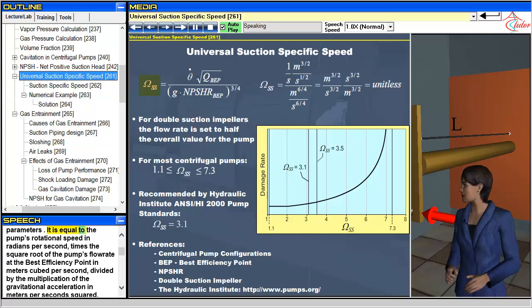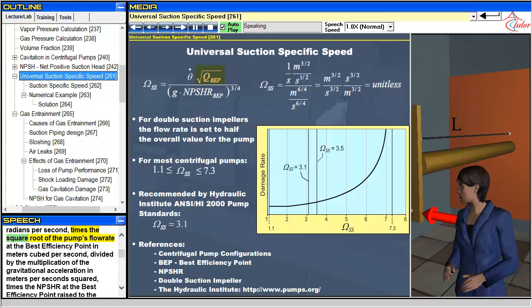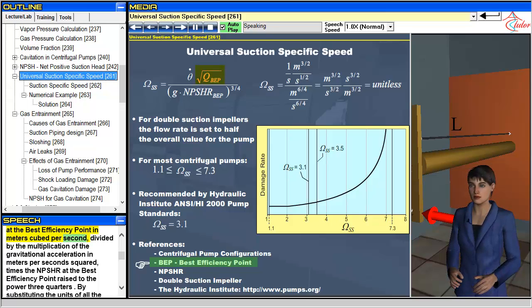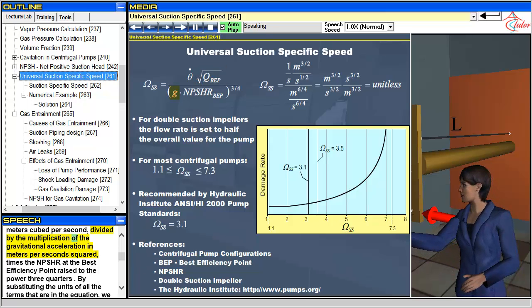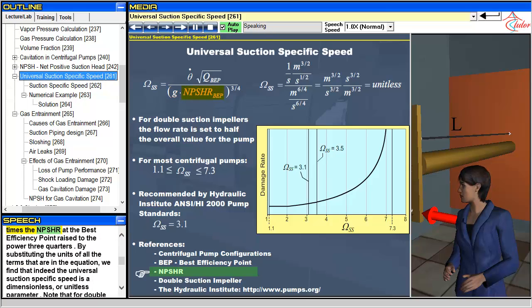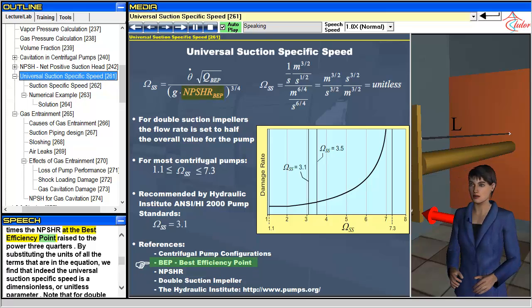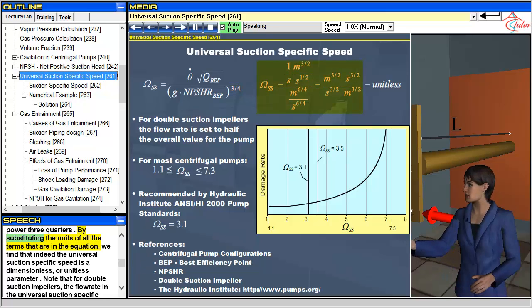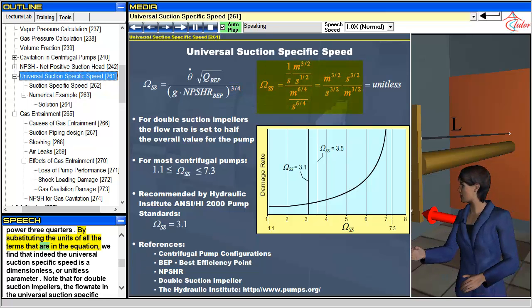It is equal to the pump's rotational speed in radians per second times the square root of the pump's flow rate at the best efficiency point in meters cubed per second, divided by the multiplication of the gravitational acceleration in meters per seconds squared times the NPSHR at the best efficiency point, raised to the power three quarters.